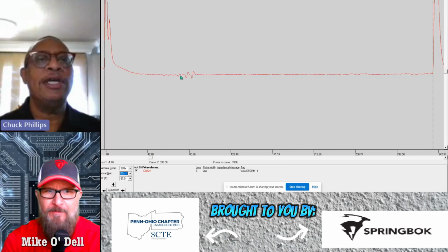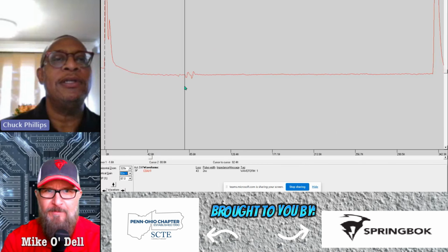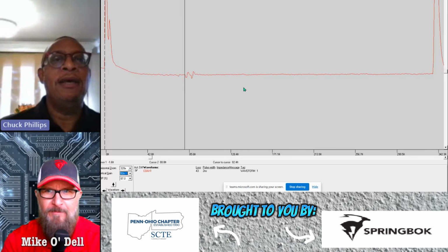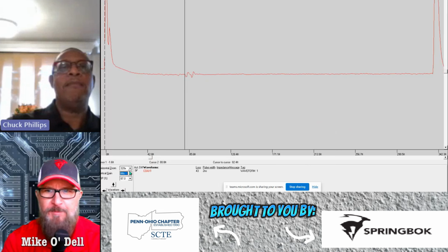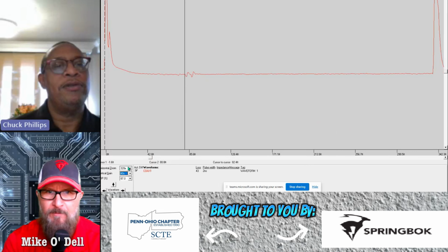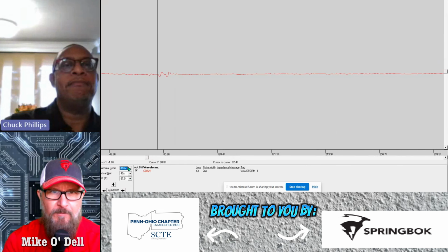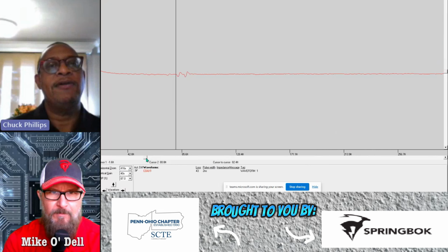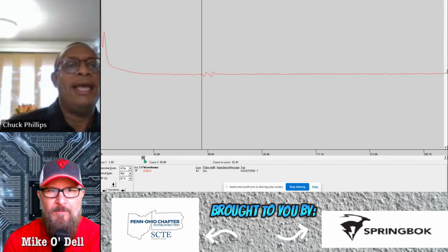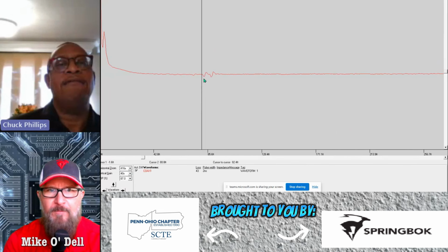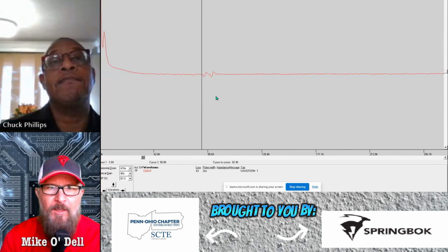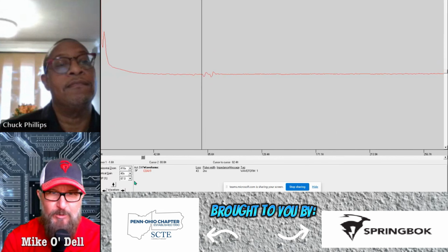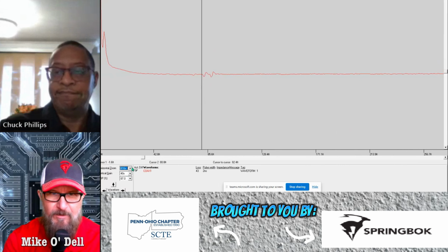Depending on which TDR you're looking at, I'm going to ask this question of my student on the other end. Mike, is it obvious to you? First thing I want to do is mark it right here, okay? And then after I mark it, I'm going to zoom in just a little bit, center this. Is it obvious that this very likely could be two separate events? This looks like it could be those two places that are fairly close together.